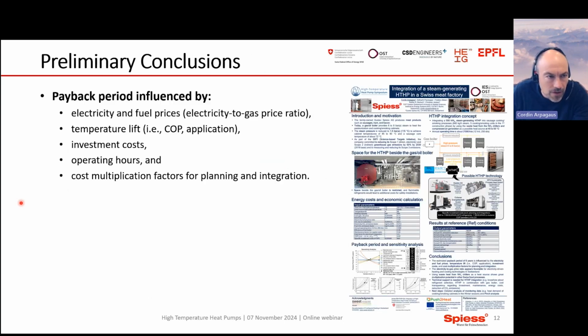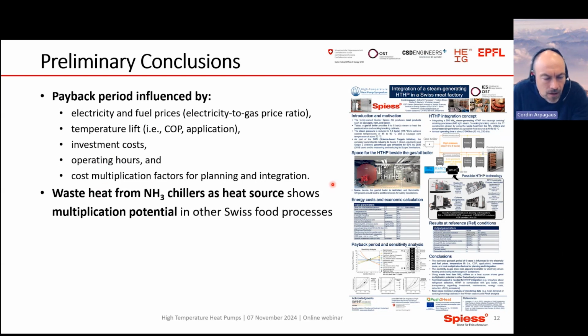So we can draw some preliminary conclusions. This was also presented in a poster at the High Temperature Heat Pump Symposium in Copenhagen. The payback period is influenced by the electricity and fuel price, by the temperature lift, by the investment cost, by the operating hours, and the cost multiplication factor for planning and integration. Waste heat from ammonia chillers as a heat source is available, and in principle this is often the case in food companies where they have electrically driven refrigeration chillers and a gas boiler, a fossil-fueled system for producing steam or hot water. So it has a lot of multiplication potential.